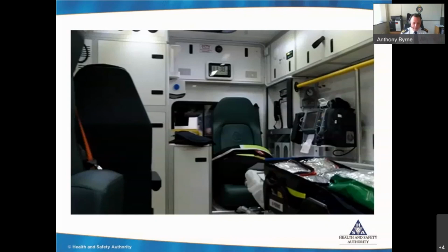We came together, met, we tried different things. We also got the vehicle manufacturer involved, obviously. This trauma wall is very specific, you can only mount, and there's metal frames behind that, so we only have certain positions in order to mount our heavy equipment on.